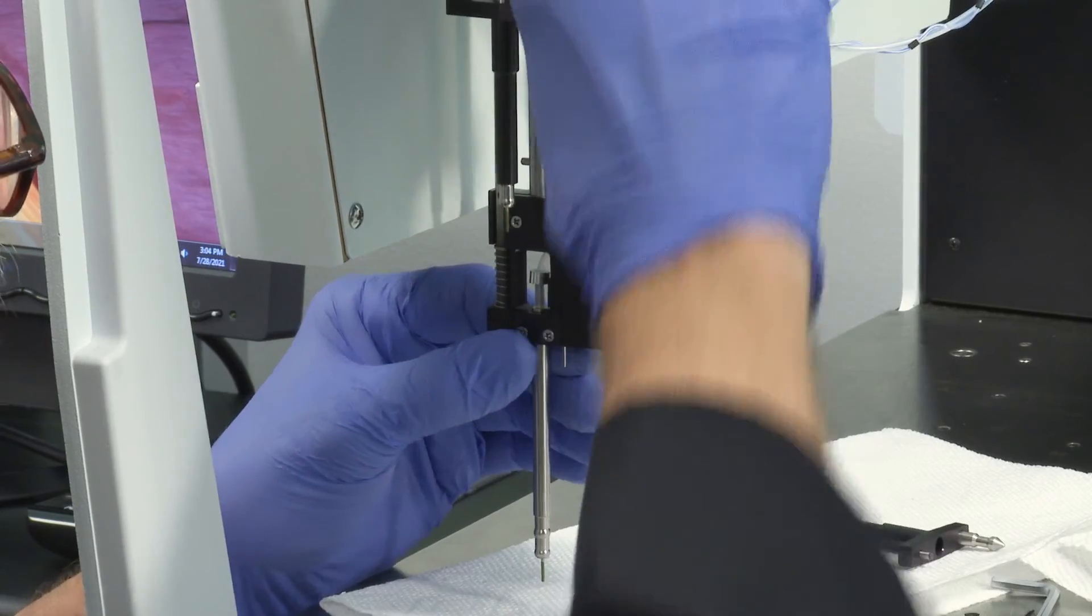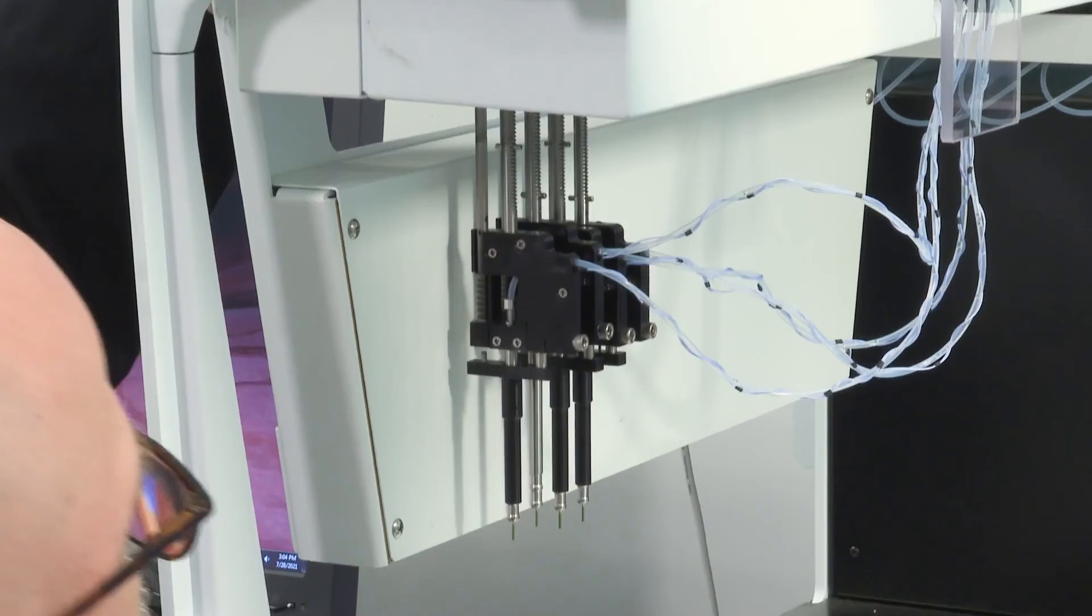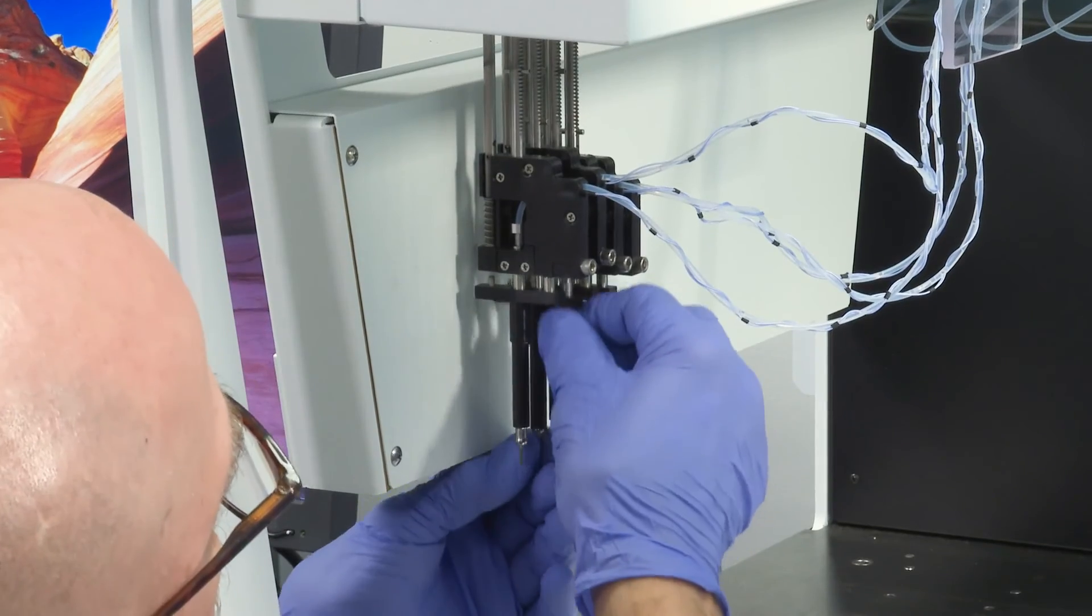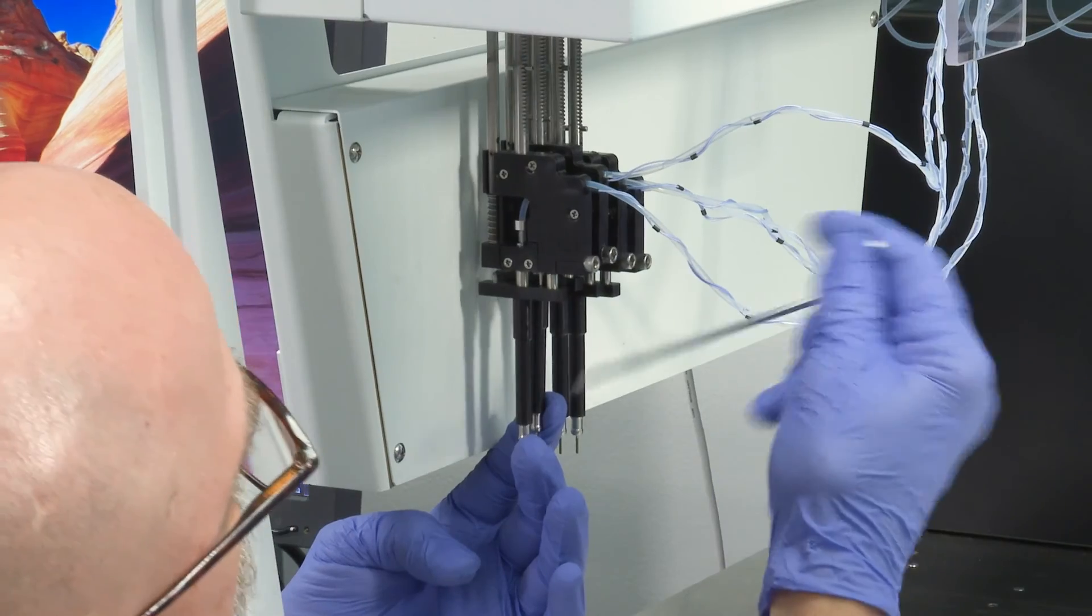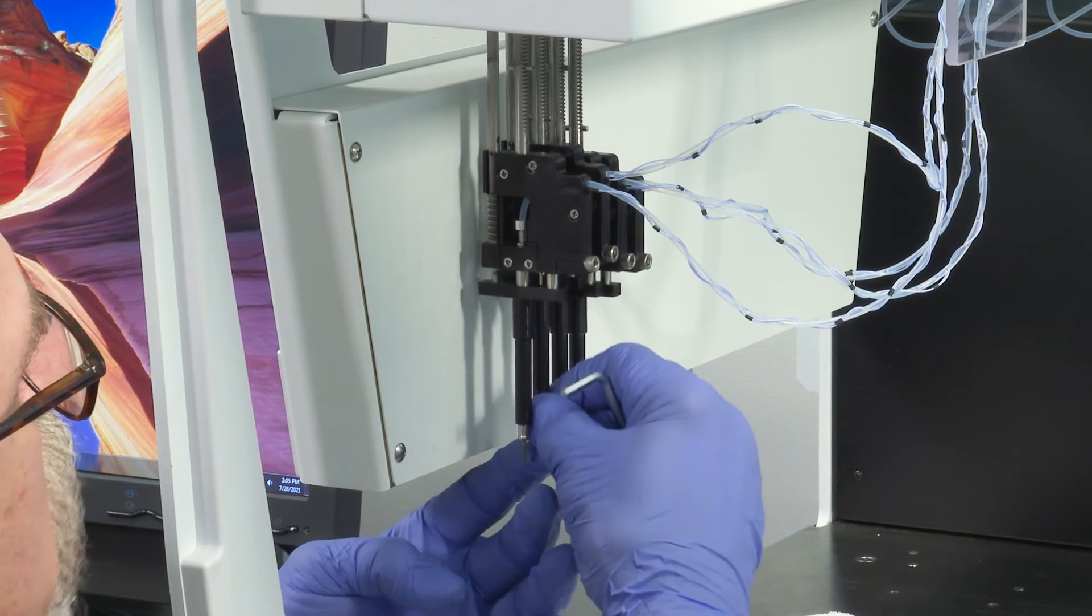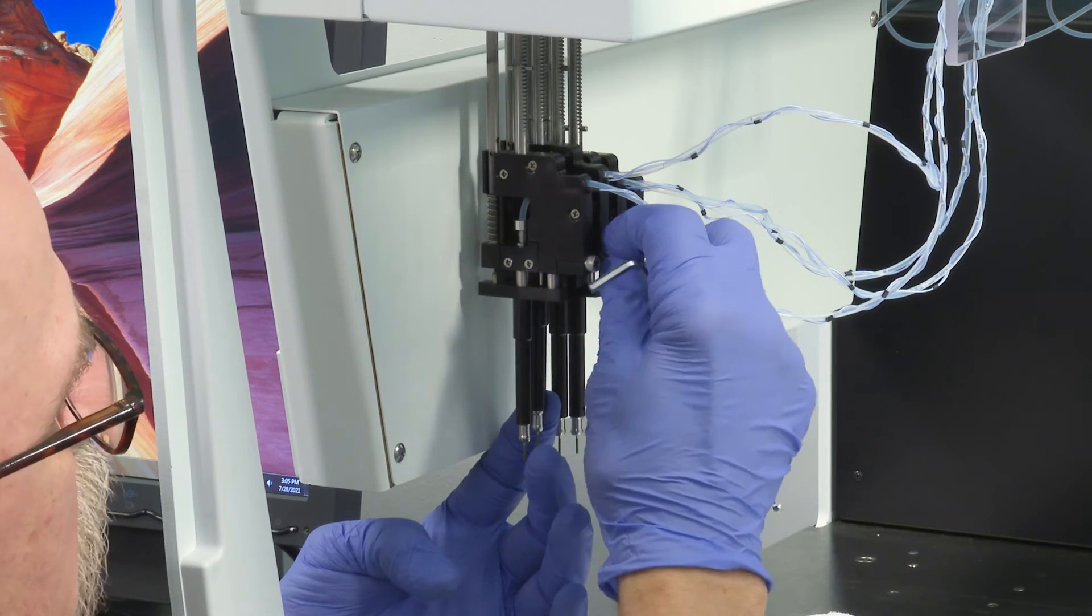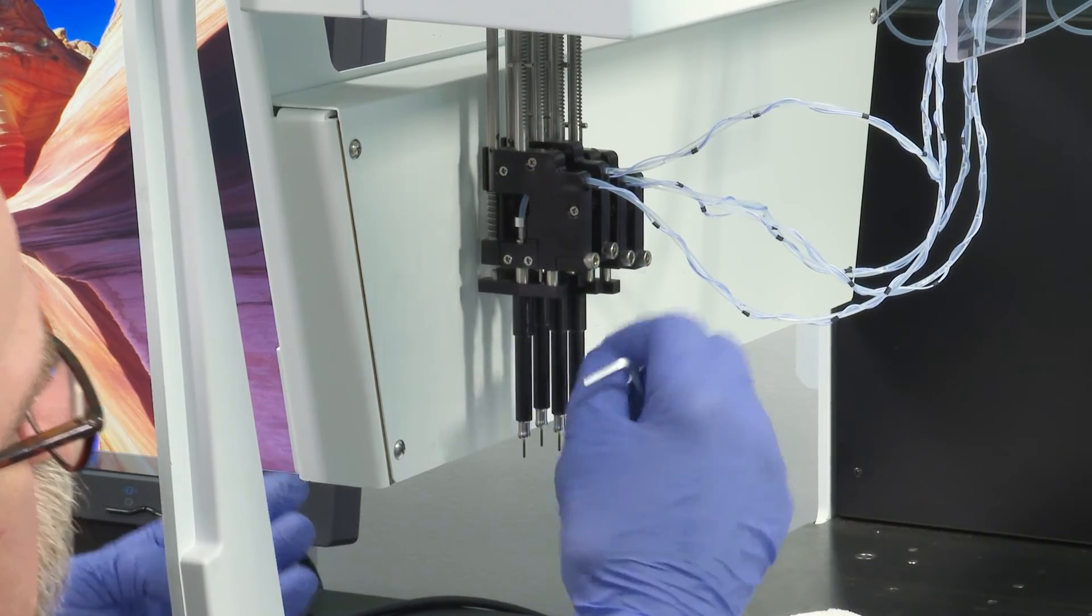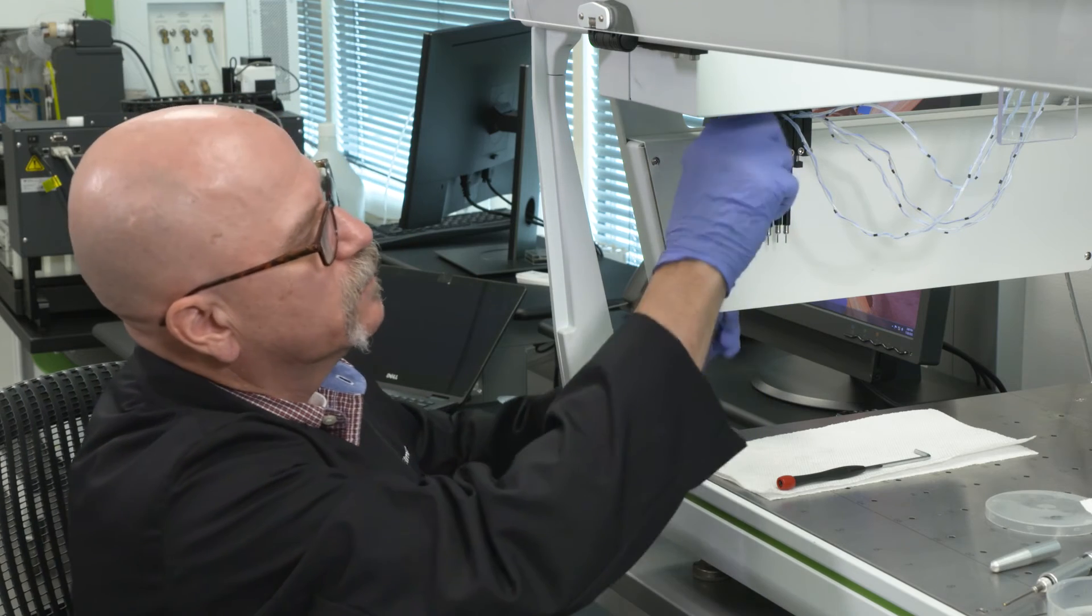And now we raise it up with the others. We pull our VersaTip, whoops. We still need to put the tip stripper back in. We just snug this cap screw here up, make sure that the tip stripper sleeve is in the full up position before you screw that in. Make sure that it moves freely and that it is settling down against the tip of the screw when you're finished. We're going to raise the tip housing to the top position and lower the others.